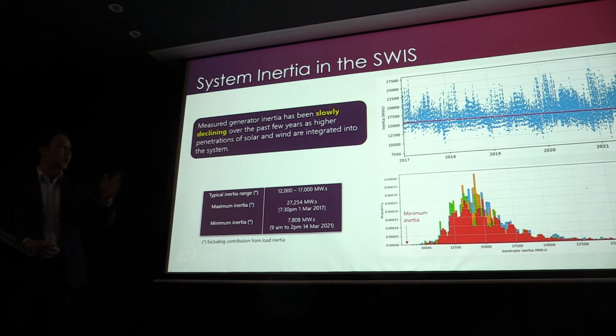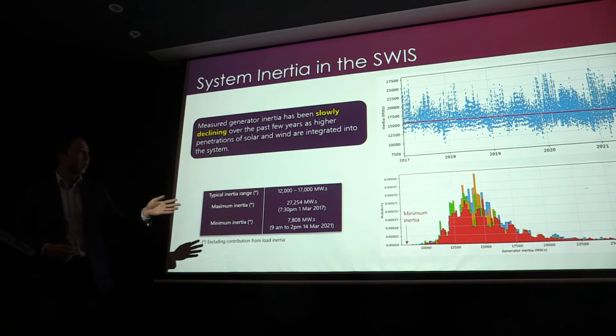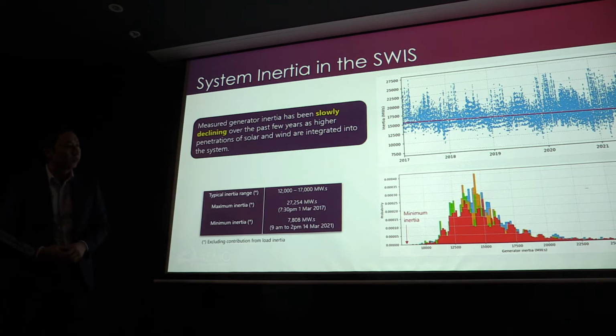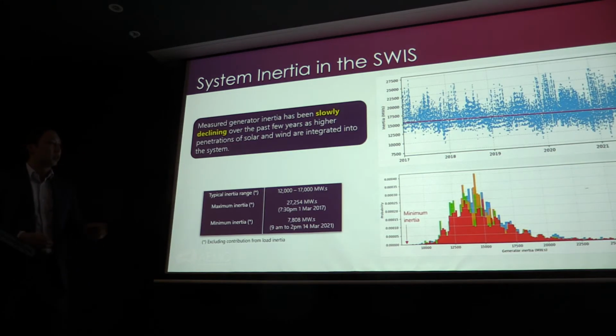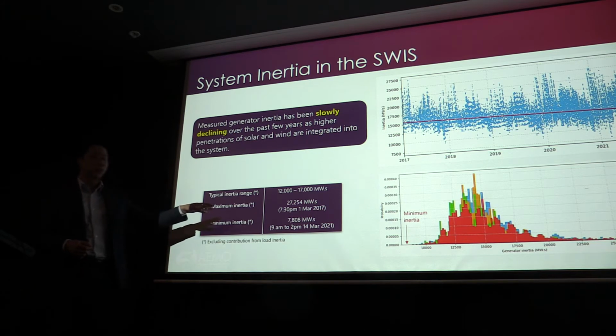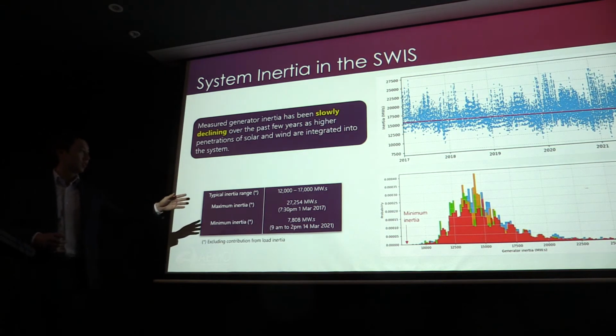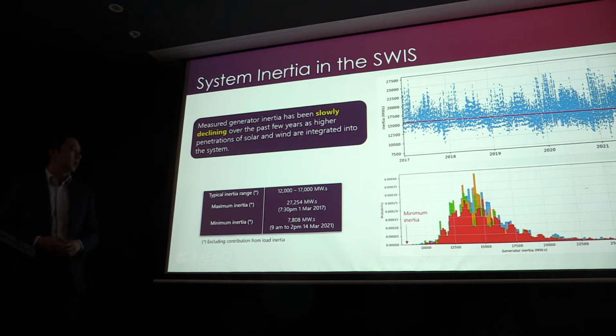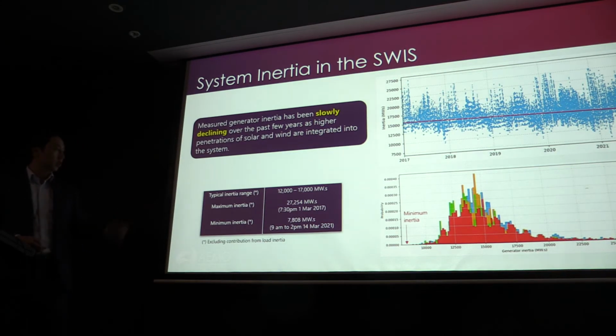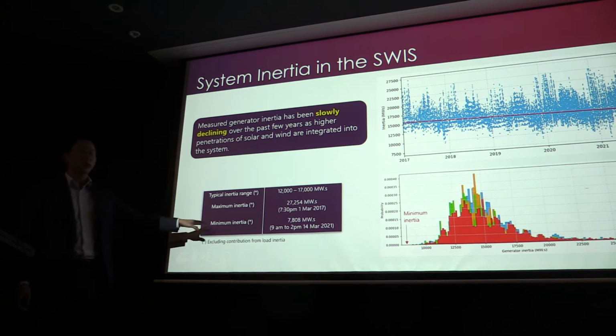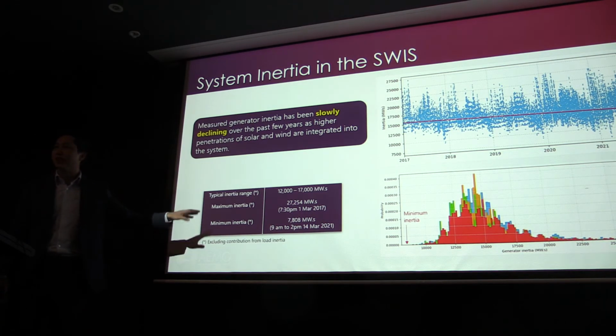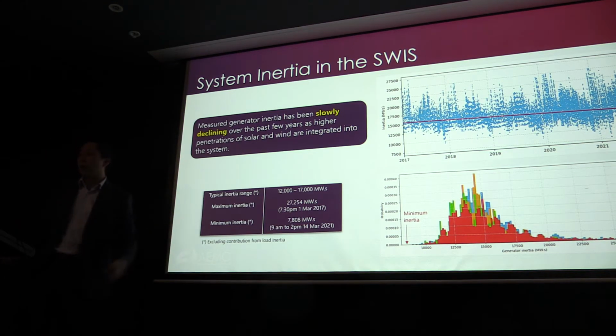And here's sort of the histograms. As I said before, it sort of ranges between the 10 and the 25, 28 mark, but most of the time it's sitting around that 15 to 20, or 12 to 20 sort of range. The maximum inertia we've ever had, as far as the records I've seen go, is about 27.2 gigawatt seconds, and the minimum is 7.8 gigawatt seconds earlier this year. And this is minimum without a contingency as well. So if we had a contingency, it'd be even lower.